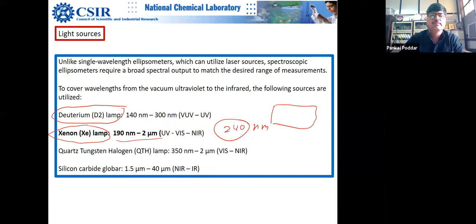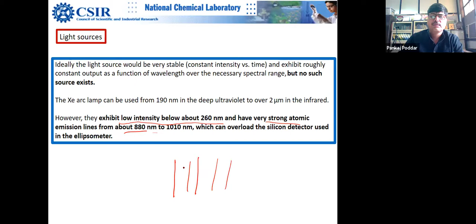As it is written, the xenon lamp starts showing low intensity below 260. Another problem with the xenon lamp is the very strong atomic emission lines, which can easily saturate the detector, because those are very strong, very sharp lines. So these things are practical.